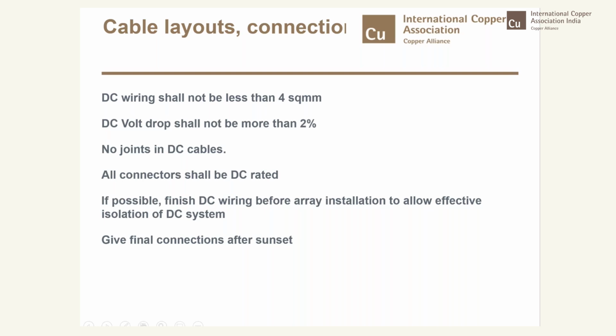How do we prepare the cable layouts and cable connections? For the DC wiring, MNRE stipulates copper conductor wires not less than 4 square mm for inter-panel wiring, and for the entire DC system the wiring shall not be less than 4 square mm, the minimum size. And you need to factor in the length so that the DC voltage drop from the array junction box to the inverter DC terminal shall not be more than 2%. Joints are not permitted in DC cables because of the voltage drop they cause. And the connectors shall also be DC rated.